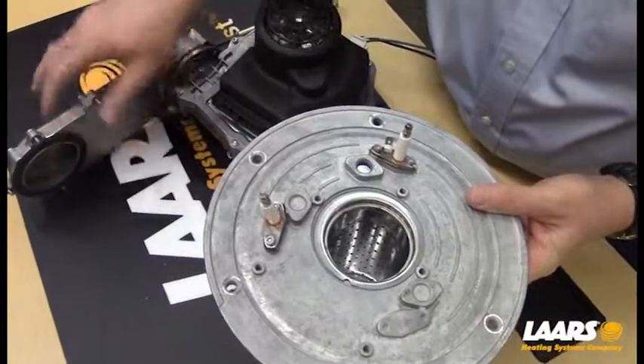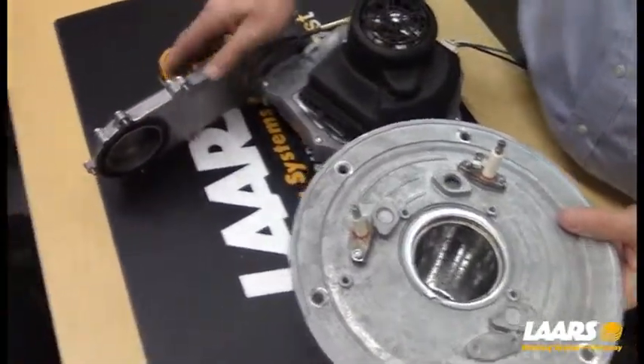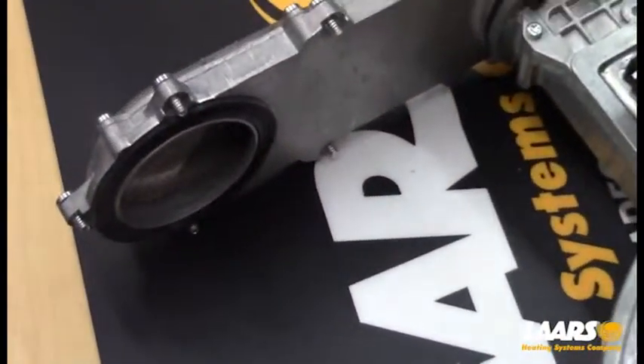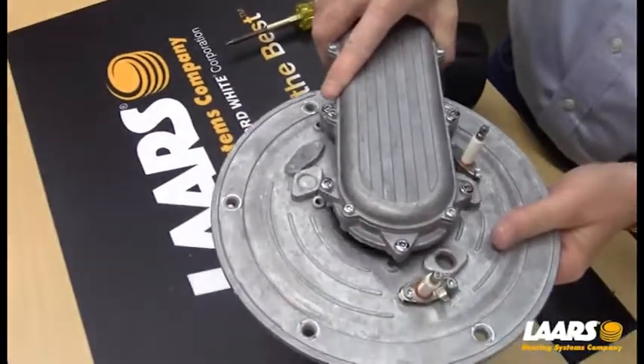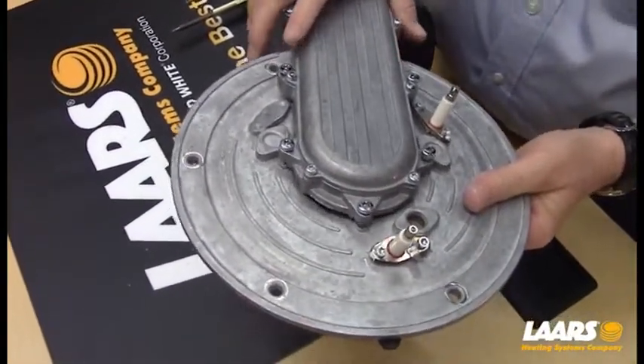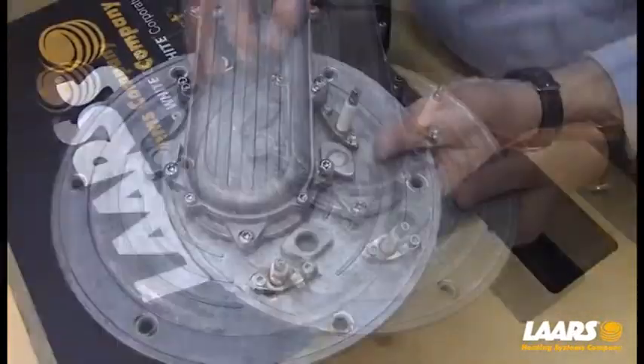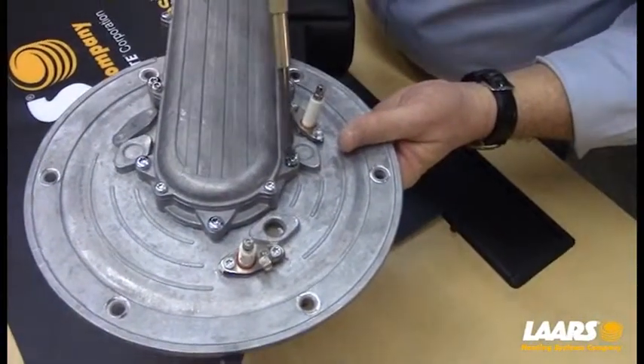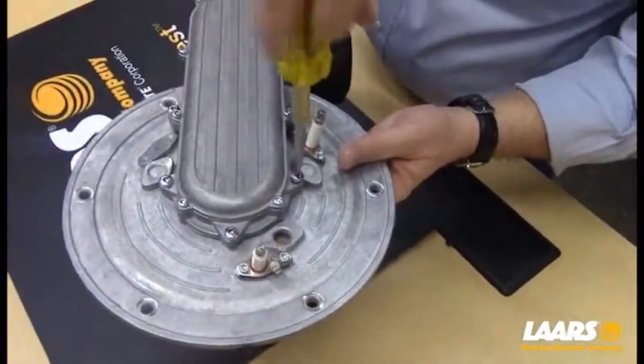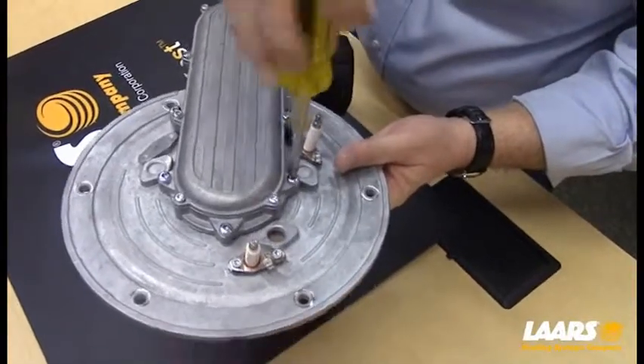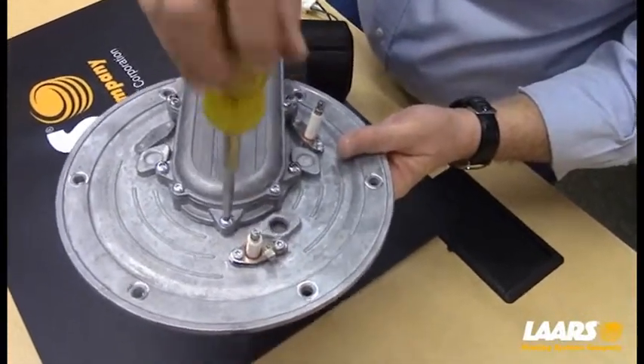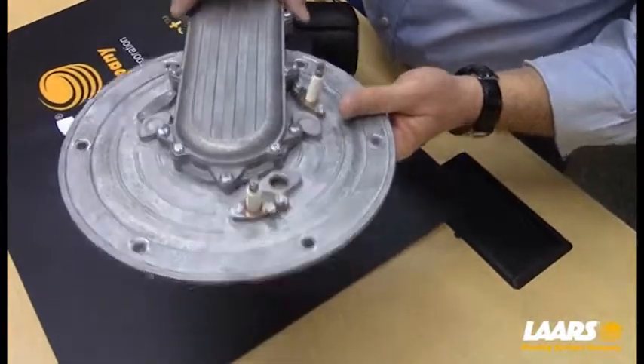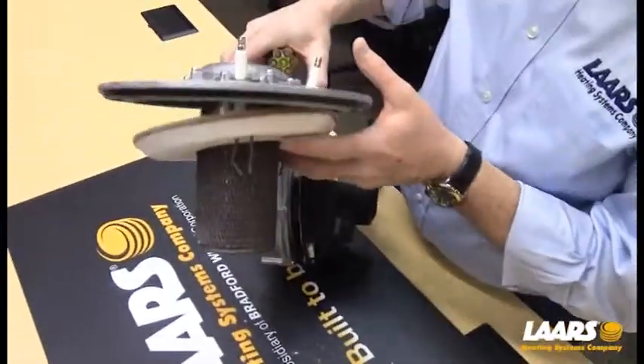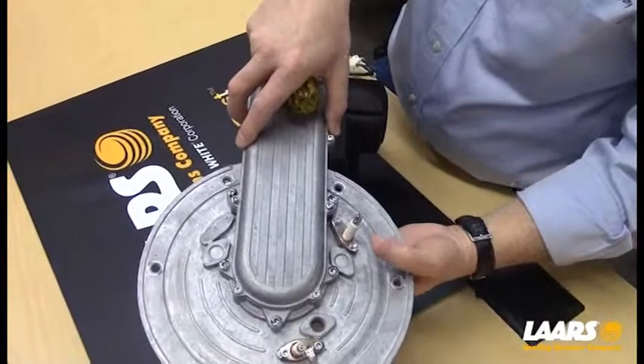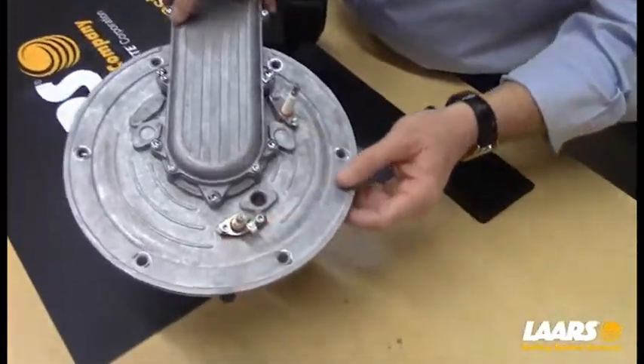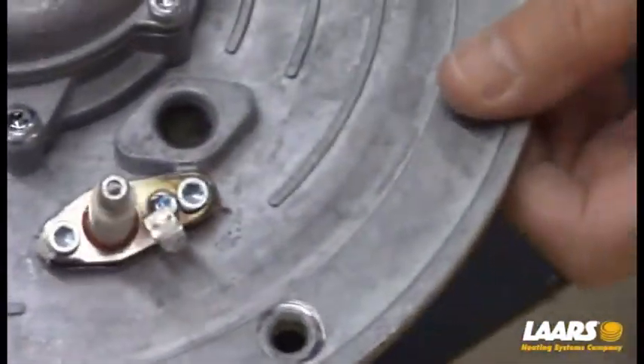Next, make sure your gasket is in place for your arm on the burner plate. Okay, line this back up and tighten the set screws. So now we're tightening the 5 number 25 Torx bits. That will hold the burner arm back into position on the plate. All right, and the next thing I want to talk about is pulling the igniter, or the flame rod. These are number 20 Torx bits. So I'm going to change my bit to a number 20.